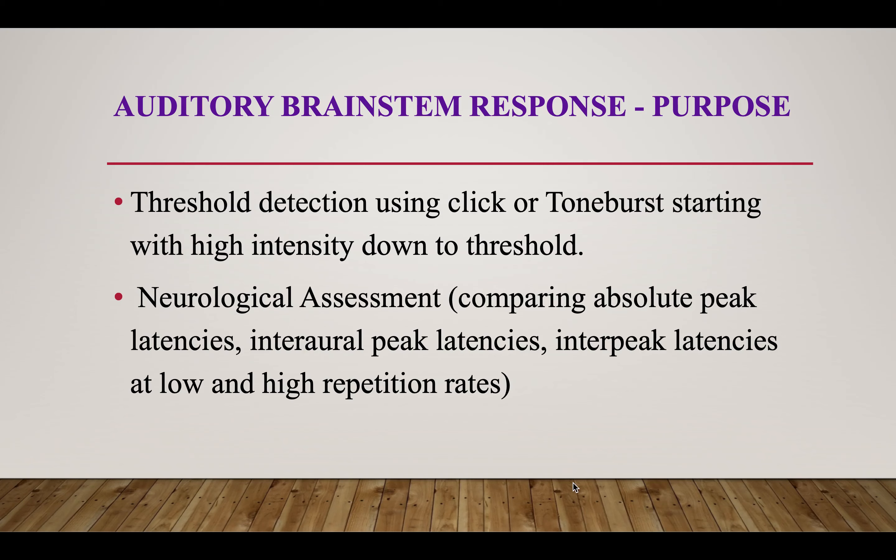Auditory Brainstem Response setup for threshold detection uses click or Toneburst, starting with high level down to threshold. Auditory neurological assessment is done by comparing absolute peak latencies, inter-aural peak latencies, and inter-peak latencies at low and high repetition rates.